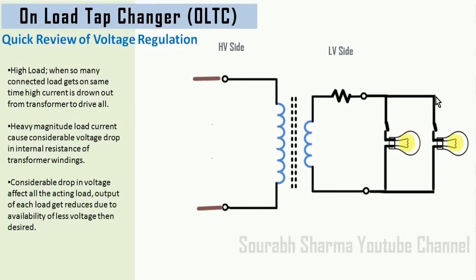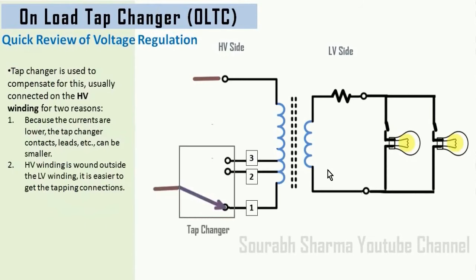Similarly, when 2 ampere current is drawn, 2 volts will be lost and we will get 8 volts at the output. This decreased voltage is most of the time not sufficient for the connected loads and can severely affect their performance. So to overcome this drop in voltage, or voltage regulation, tappings are used in the transformer winding. A number of connections are taken out from in-between turns at regular intervals.